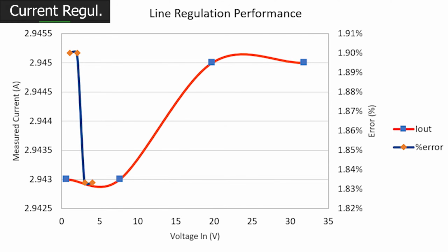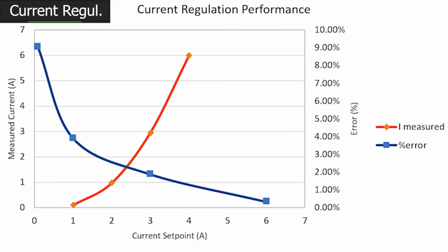The base accuracy isn't fantastic or good or great, and I want to dive a little more into why in a moment. I see two effects. The primary error cause is the offsets of the system — the tolerances of the voltage reference, the shunt resistor tolerance, the ADC errors — that's basically it. But there might be a secondary effect. That primary effect is what we see slowly trending towards zero error as current increases.